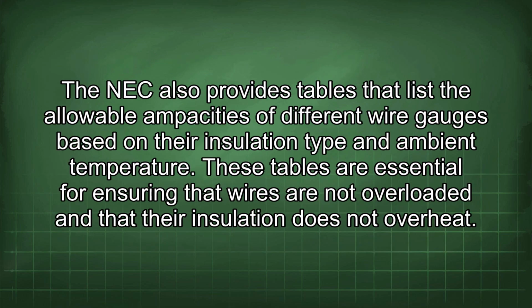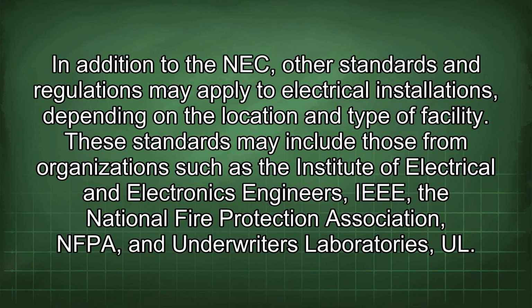The NEC also provides tables that list the allowable ampacities of different wire gauges based on their insulation type and ambient temperature. These tables are essential for ensuring that wires are not overloaded and that their insulation does not overheat. In addition to the NEC, other standards and regulations may apply to electrical installations depending on the location and type of facility. These standards may include those from organizations such as the Institute of Electrical and Electronics Engineers, IEEE, the National Fire Protection Association, NFPA, and Underwriters Laboratories, UL.